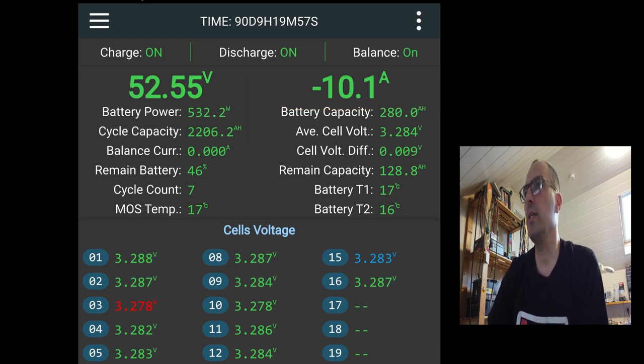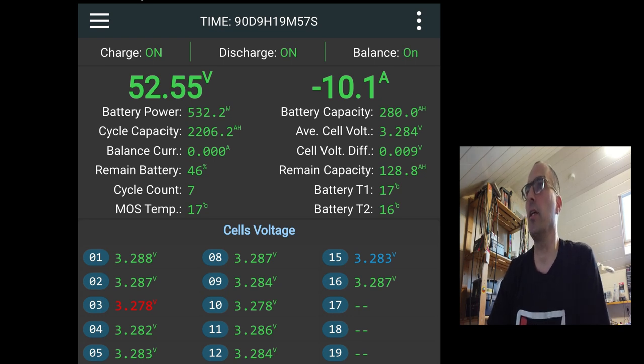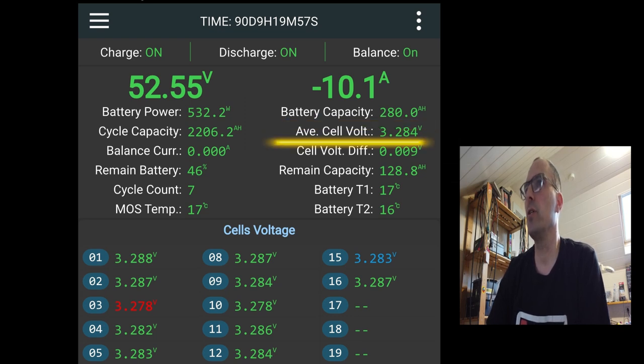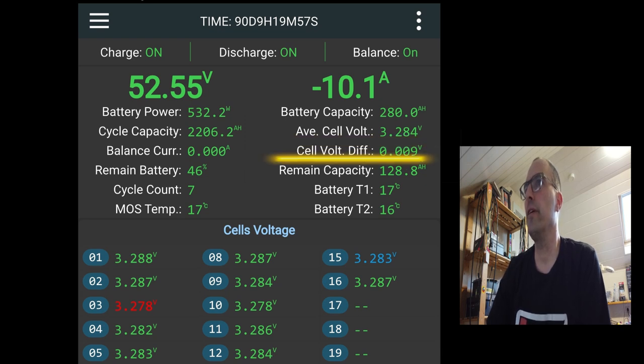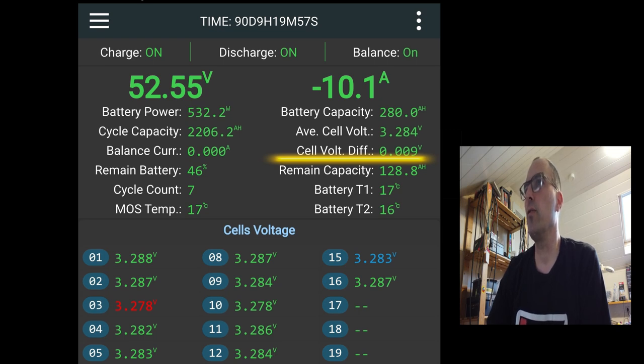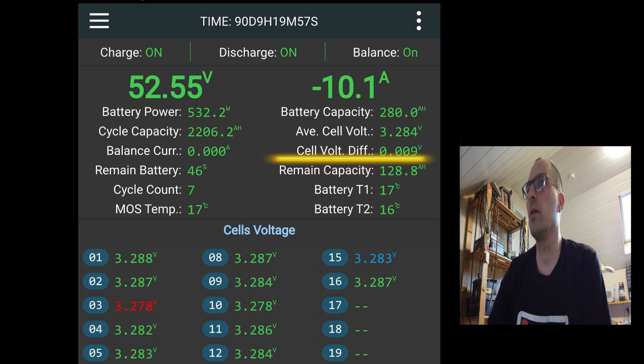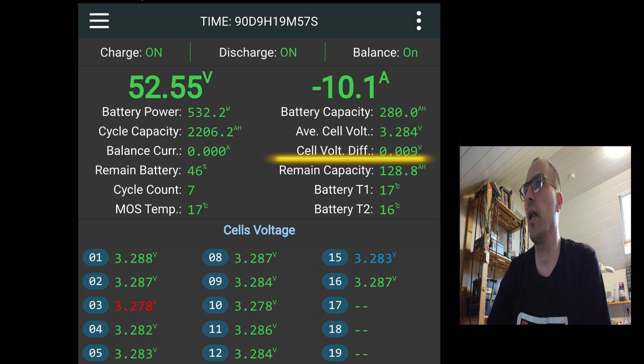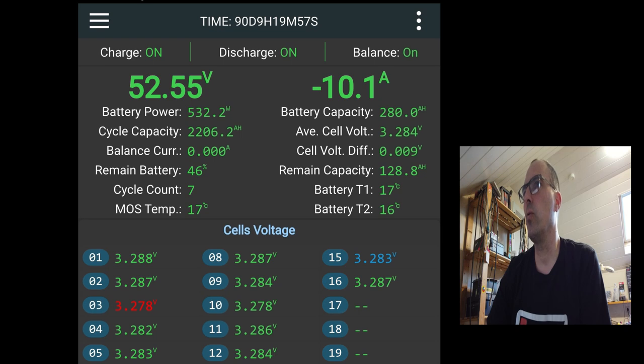The battery capacity is 280 amp hours. This is a setting you have to manually introduce in the BMS. The average cell voltage, 3.284 volts. The cell voltage difference between your 16 cells is the highest cell voltage and the lowest cell voltage. That difference is 0.009 volts. So all cells are matched. They're close to each other. But of course, it's pretty normal because they're in the 3.28 voltage zone. And as you know, we have a very flat curve when using LiFePO4 batteries.